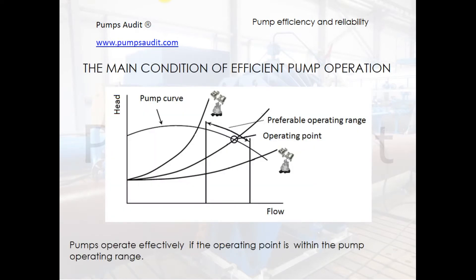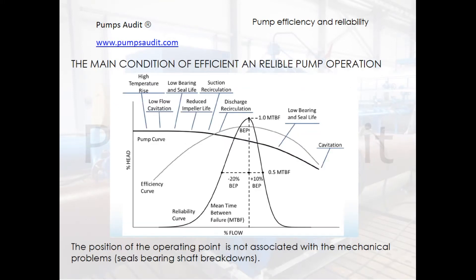The answer is quite simple: the pump operates effectively if the operating point is within the pump's operating range. If the operating point lies outside the operating range, the pump operates with low efficiency. The same applies to pump reliability — very often pump users do not connect mechanical problems with the position of the operating point.